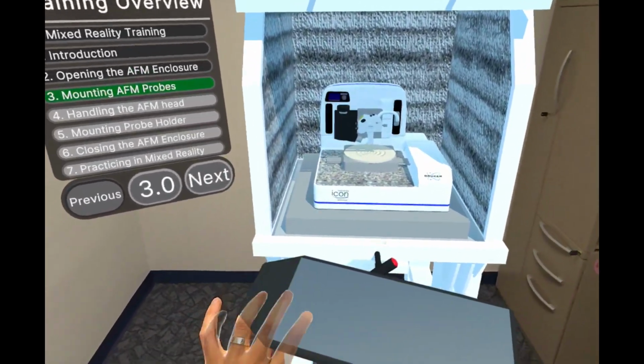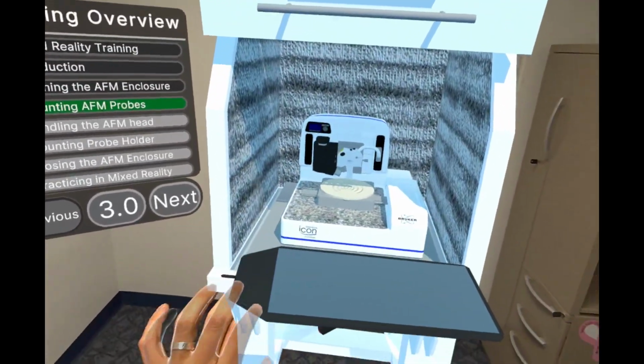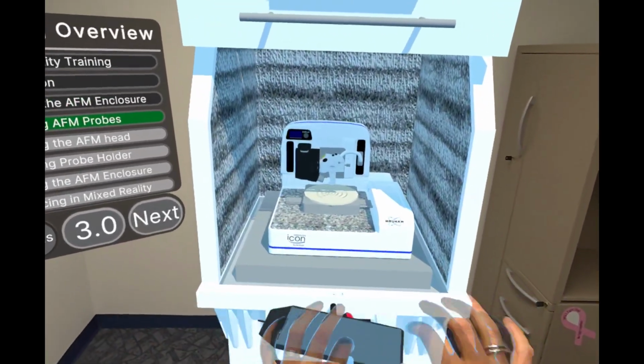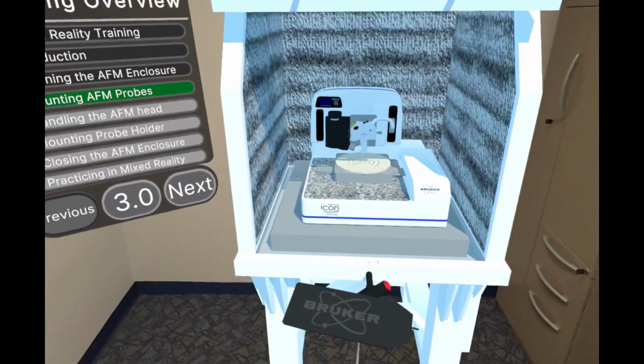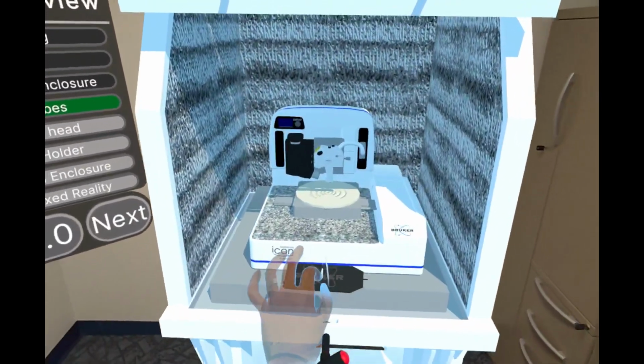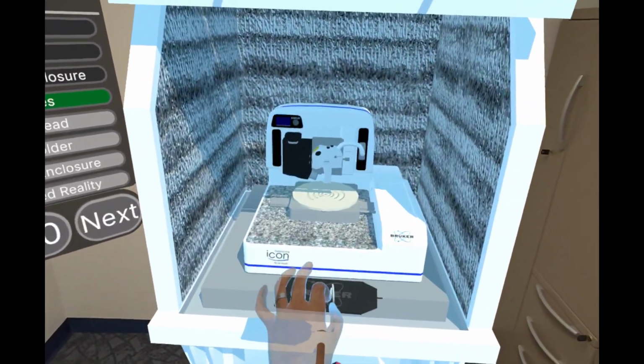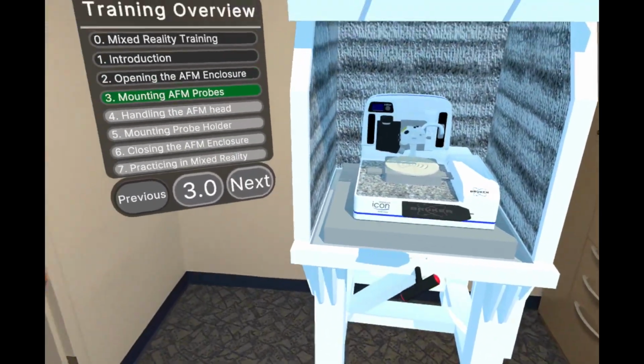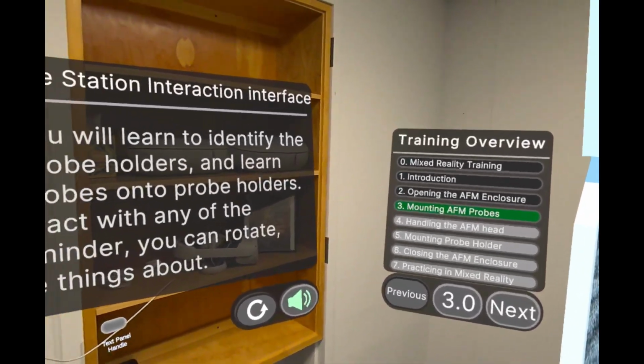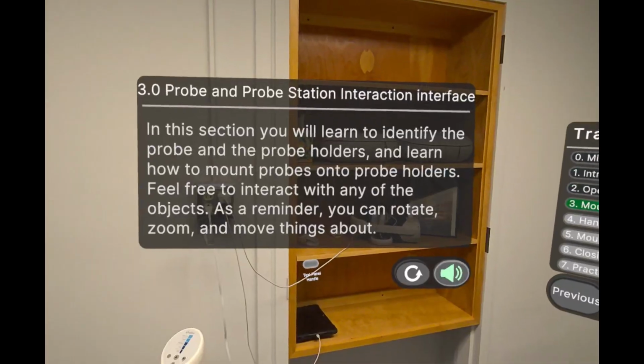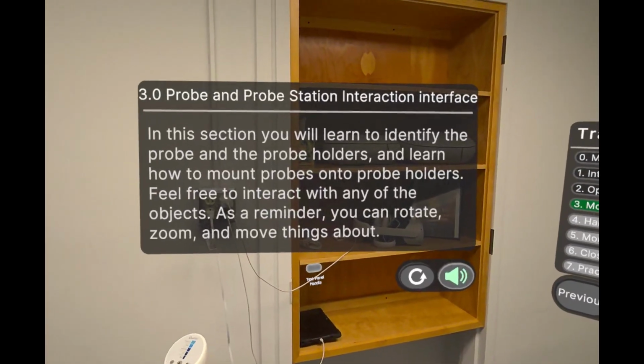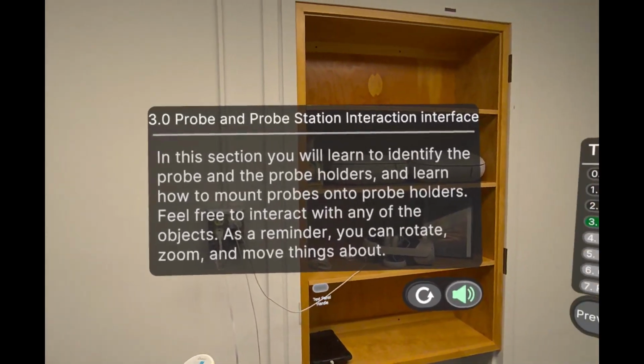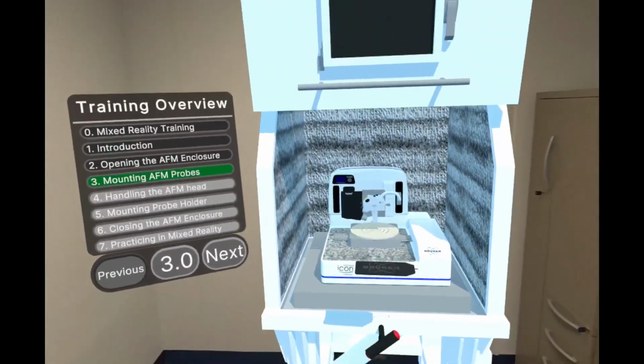The probe cantilevers are extremely fragile, and even brushing against your glove is enough to break them. Each probe costs from as cheap as $15 a probe to as expensive as $4,000 a probe. Typical topography probes are about $30, so it's not very expensive to lose a probe now and then, but repeatedly breaking them or dropping them can add up.